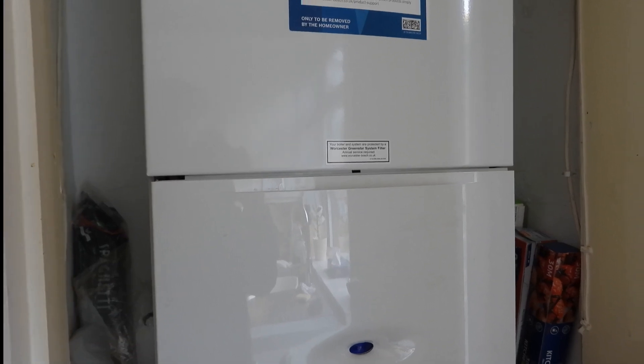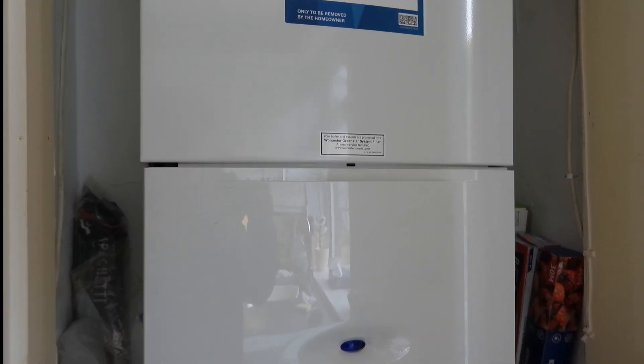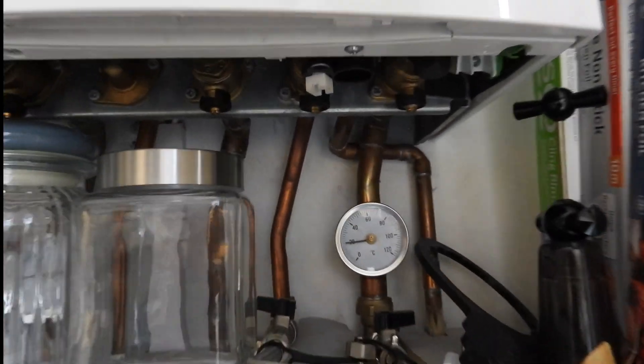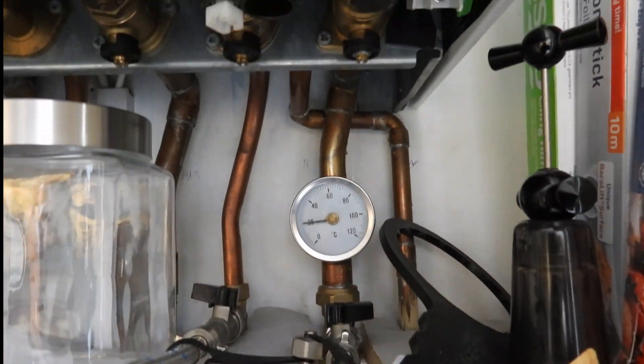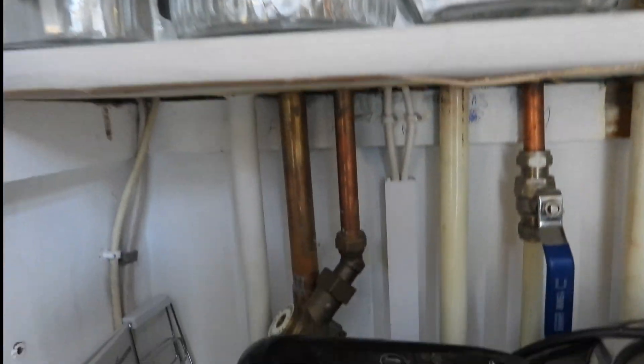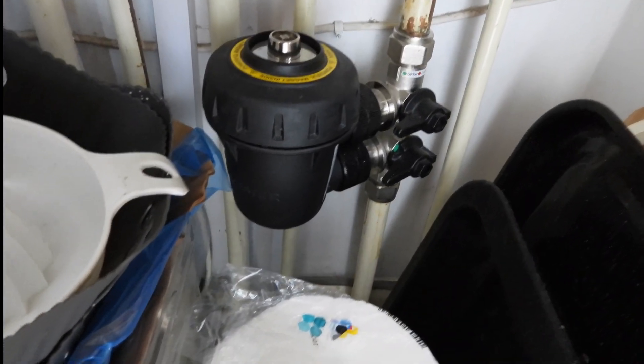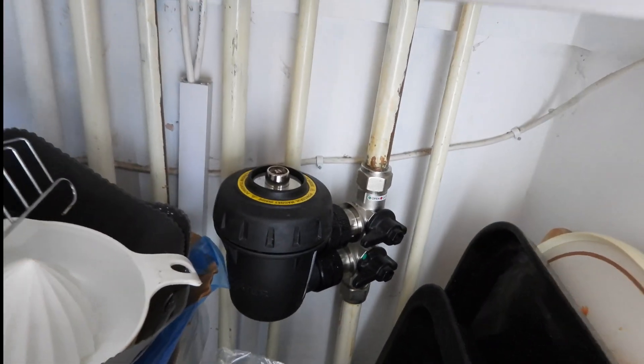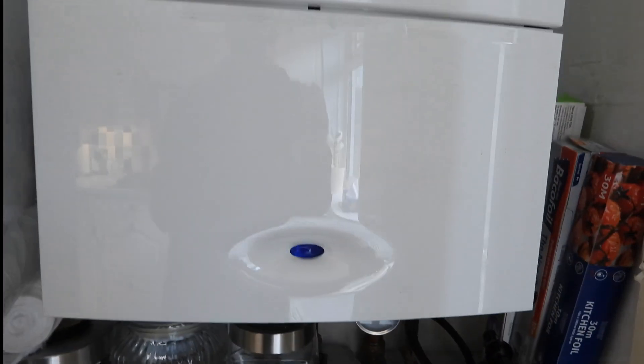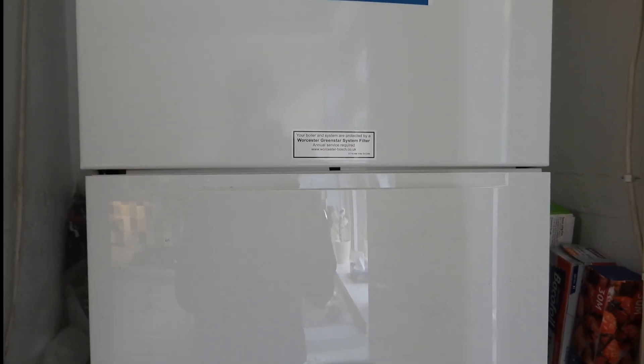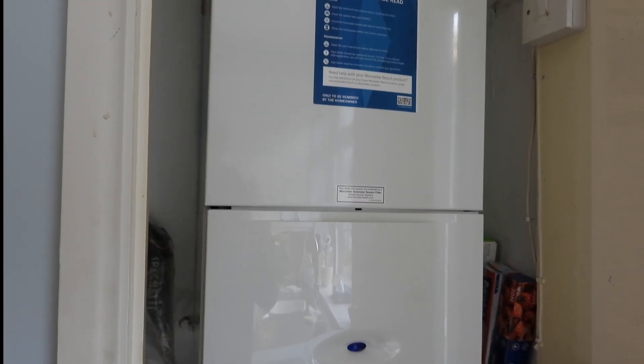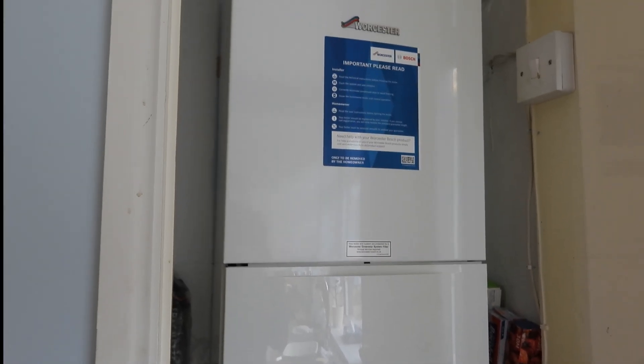Now my combi boiler system here consists of a one-pipe system, so the pipes come out of the boiler. They're in three-quarters for the return there and just behind this door here there's the flow. So they come down here and go down through the floor, and they run completely around my entire bungalow in 22mm because I've got a one-pipe system. The 22mm pipe is staying unreduced all the way around, just teeing off to each rad as it goes along.